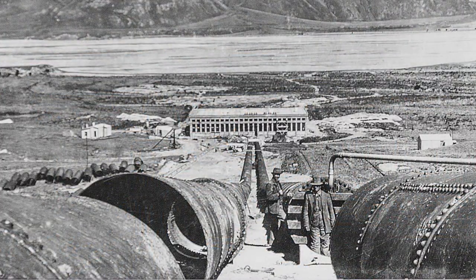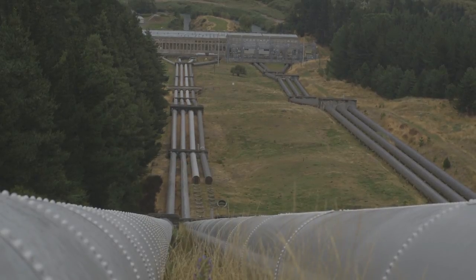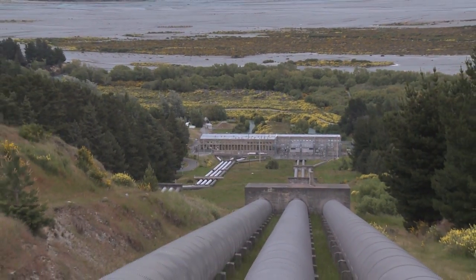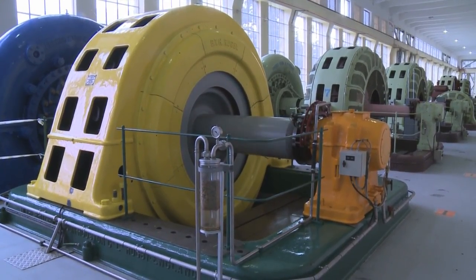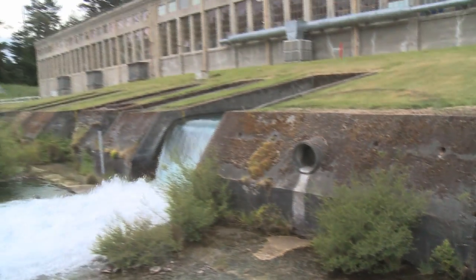There are two different styles: 1.32 metres diameter for the original four, two of which we now use, and three of 2.5 metre diameter, which feed the newer and larger machines. That flow plus pressure gives us the power out of those turbines. The energy is taken out of it and it discharges to the tailrace and then flows out to the mighty Rakaia.